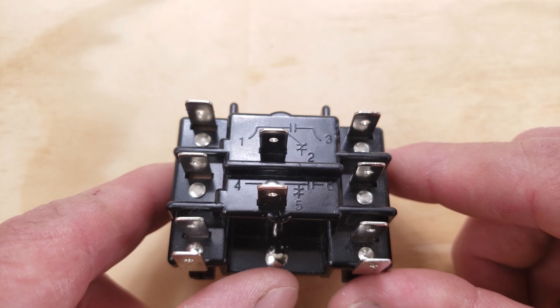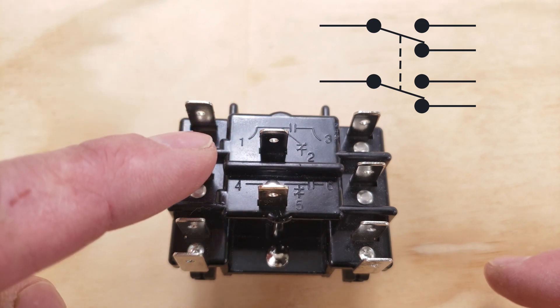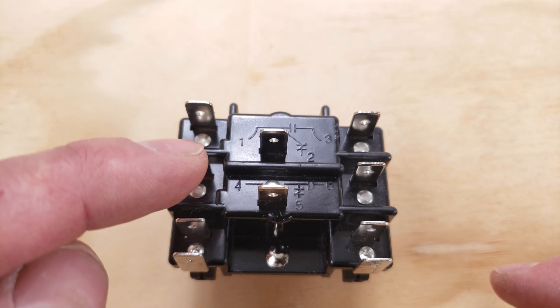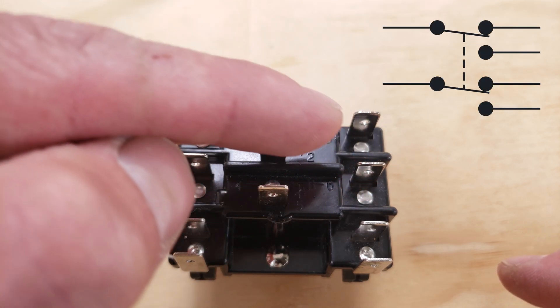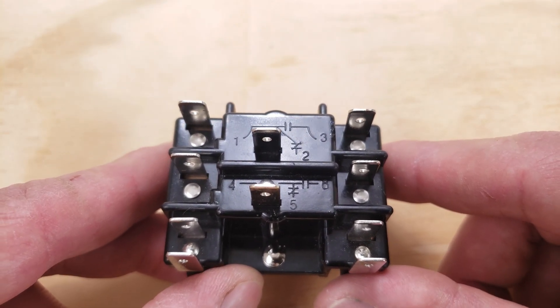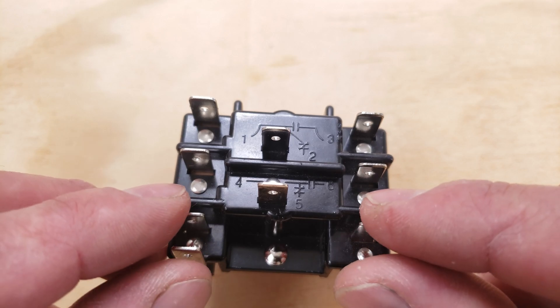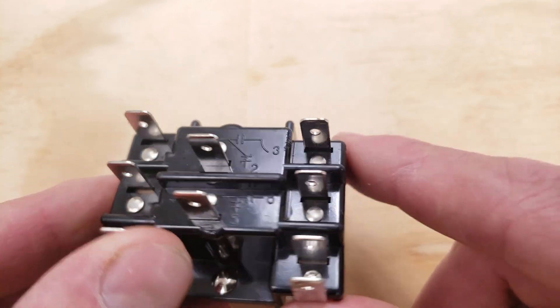Next up you have a general purpose relay that's a DPDT — double pole double throw. This is one switch or pole, and this is another switch or pole. Here is your common connection point for one, and here's your common connection point for the other, and it goes back and forth between two tabs for each. The wiring diagram on top of the general purpose relay shows the non-powered state — anytime you see a wiring diagram it's when the switch is not activated. You'd activate the switch by powering the coil on these tabs.